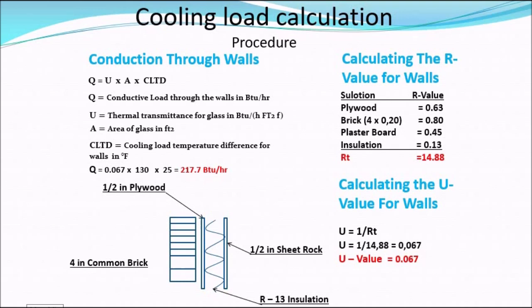Here is an example. I have calculated a total R-value of 14.88. To find the U-value, we take the reciprocal: 1 ÷ 14.88 = 0.067. That is our U-value for our walls. We can now calculate the conduction through our walls: Q = 0.067 × 130 × 25 = 217.7 BTU/hr. That is our conduction load for the walls.